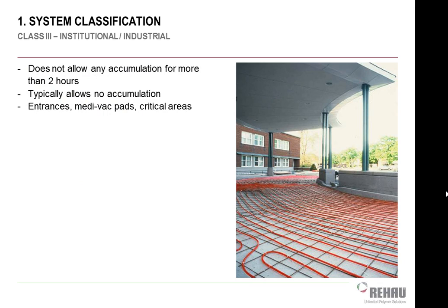Then the last type would be Class 3 systems, which would be what we use for institutional type facilities. Specifically, the most common examples are going to be emergency room pull-ups for hospitals. They're going to be helicopter pads, things like that, where we are willing to spend the extra money to get the bigger boiler system, willing to spend the extra money to run it more hours of the year in order to make sure that we have absolutely no snow and ice on the ground at all.